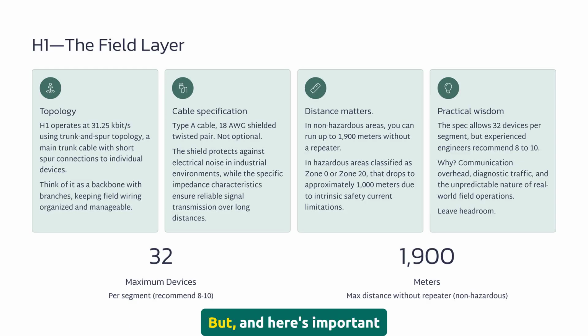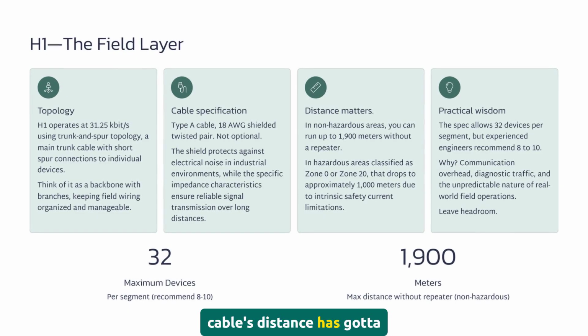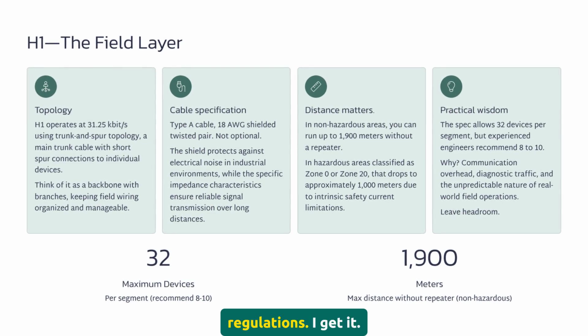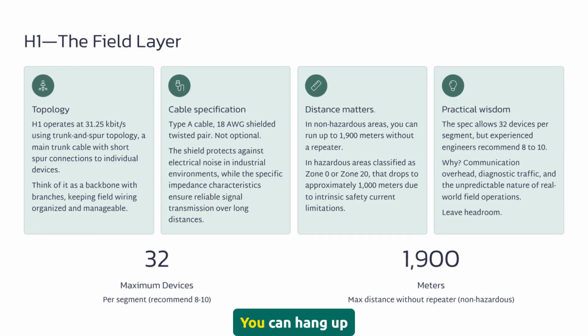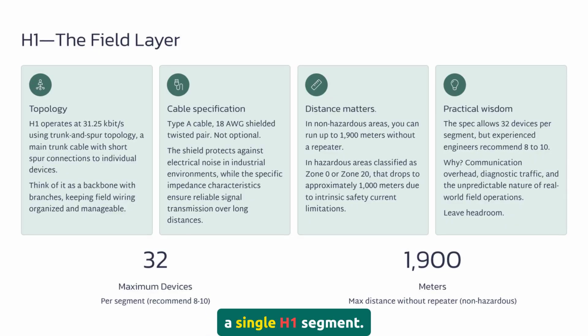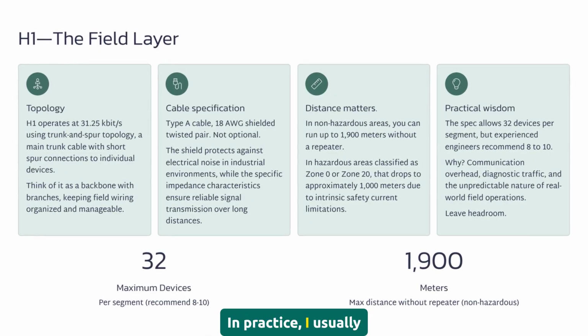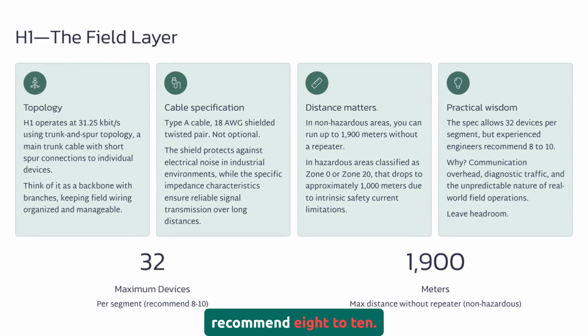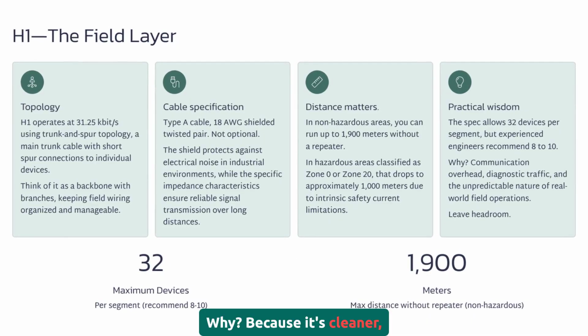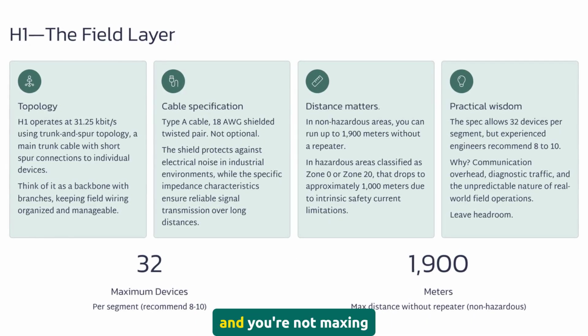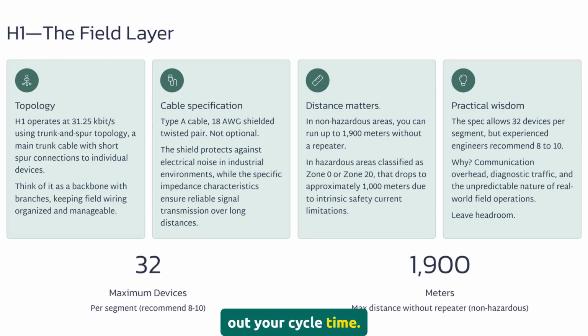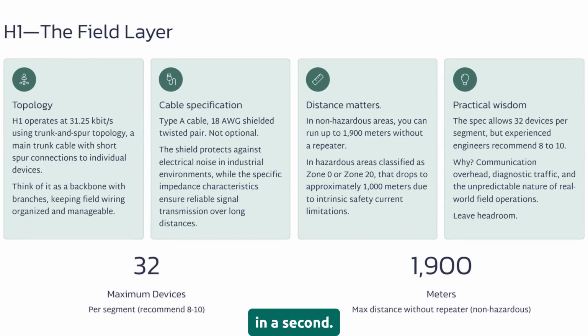But, and here's an important item, in hazardous areas, zone 0 or zone 20, intrinsically safe stuff, your distance drops. You're looking at about 1,000 meters max. The cable's distance has got to be more careful. Safety regulations. I get it. You can hang up to 32 devices on a single H1 segment. In practice, I usually recommend 8 to 10. Why? Because it's cleaner, it's easier to troubleshoot, and you're not maxing out your cycle time. We'll talk about that in a second.